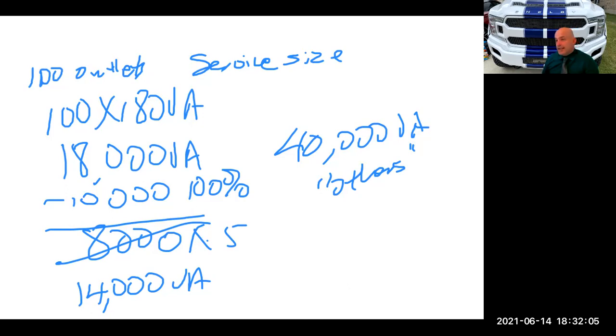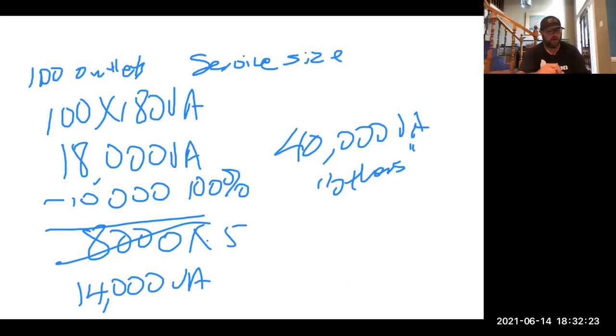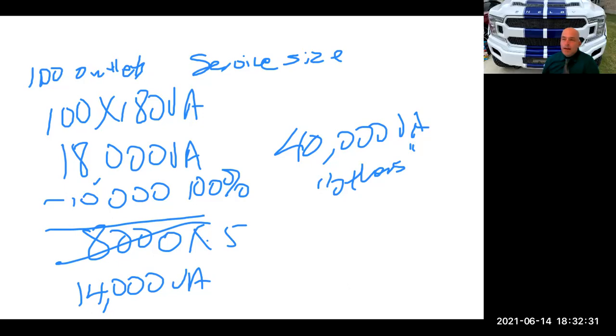And then the second note in K says, look, you can't be less than the square footage of the place times 1 VA per square foot. That's the problem in this case if I don't know what the square footage is. What if it's a 16,000 square foot office building? I'm probably just misremembering the entirety of the question. Without that square footage, it makes it real hard to apply K correctly. I almost always would know it in reality, but on a test, if I don't, I'm almost hesitant to even take the derating. I may just leave it at 18,000 and call it a day, because then I don't really know where it's safe to stop my deratable number.